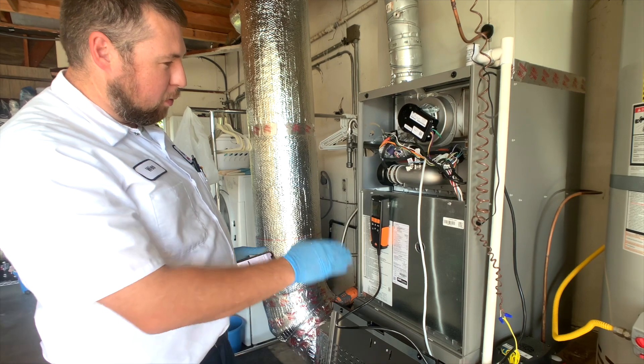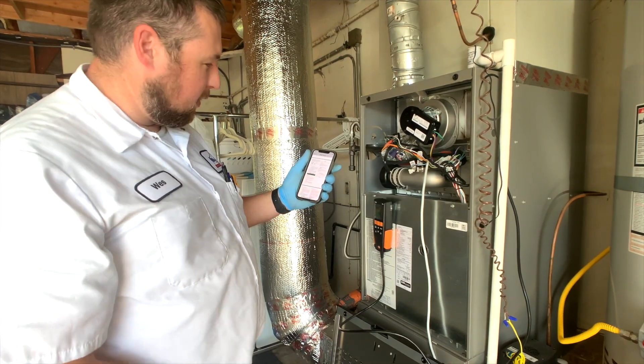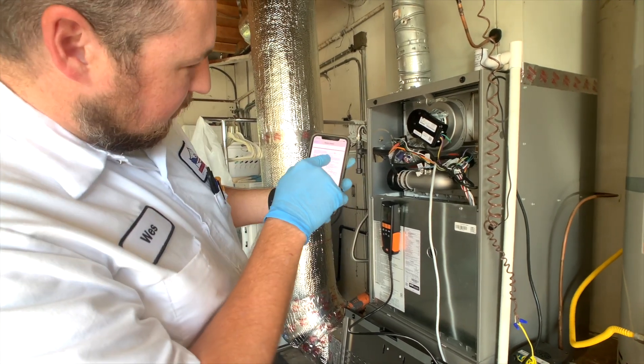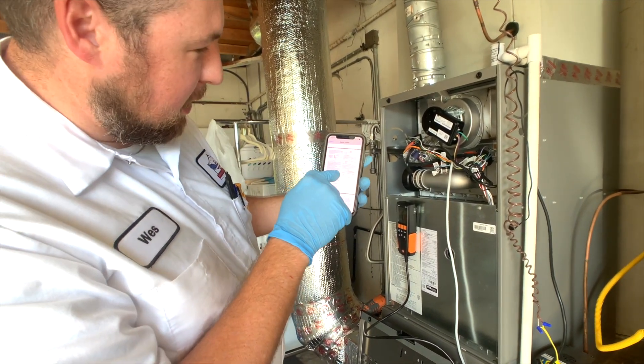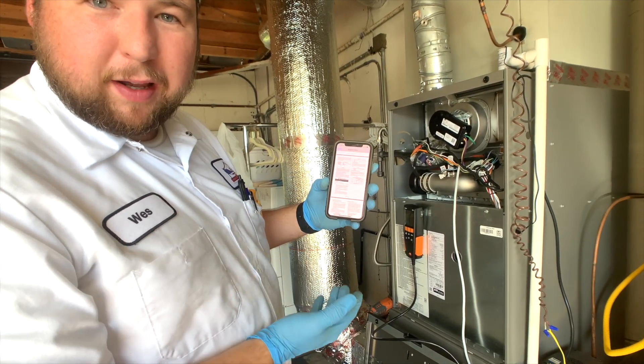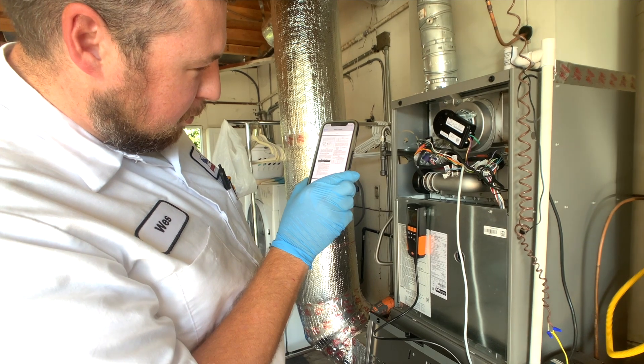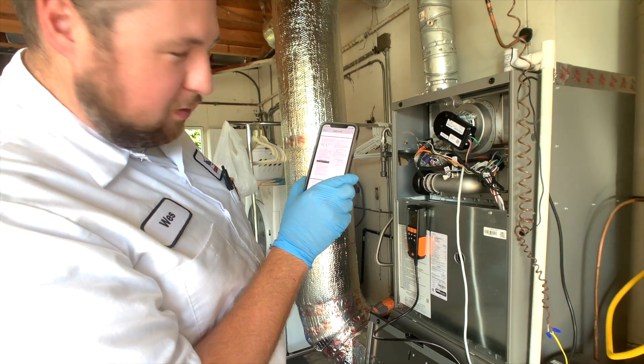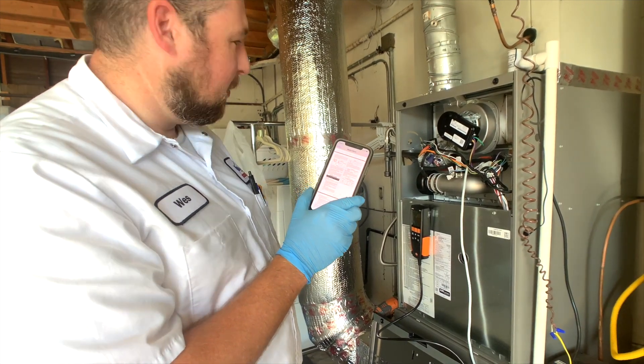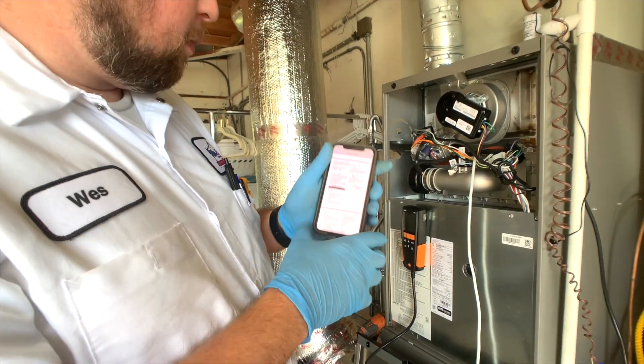You're going to want to look at your install manual under startup. This is an SL280 — it's a two-stage. You can find the instruction manual on lennoxpro.com. It tells me what our gas pressure is supposed to be at and also what our CO percentage for natural gas is. For high fire, it's 3.2 to 3.6 inches of water column for gas pressure. On low fire, it's 1.3 to 1.7 inches of water column. It also shows us our CO — we want to be between 6.0 and 7.5.